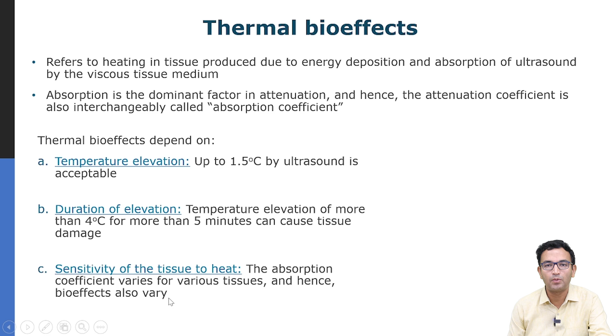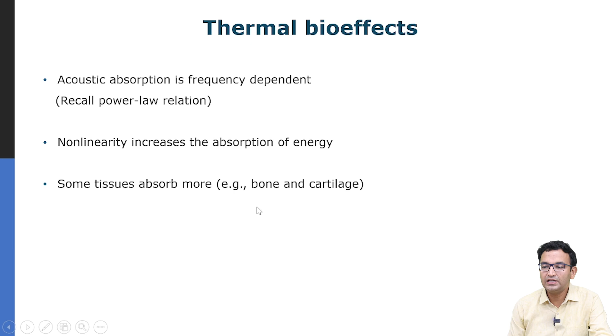If the beam has the fundamental signal as well as the harmonics, then the attenuation will increase, because these high frequency components in the form of harmonics will be absorbed more. And also consider that certain tissues absorb more heat than others. For example, bone and cartilage absorb more heat and get temperature elevation very quickly. So, all these factors should be kept in mind while performing imaging.